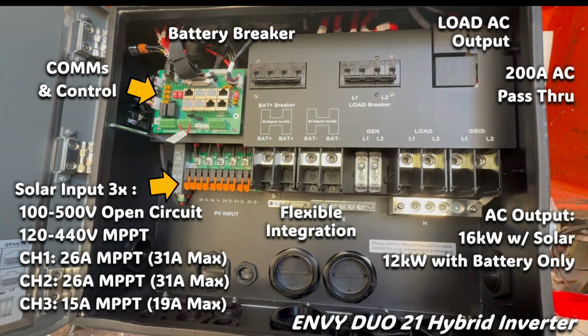Next up, the comms and control board allows you to have inverter communication to battery, the CT current transducers on your line for self-consumption, and then parallel connections if you have more than one inverter. Next up, the battery breaker. This is built into the inverter and allows connection of the battery system. You can see you have 2 positive battery connection terminals and 2 negative battery terminal connections. The battery terminals can handle about 4/0 copper. It's actually metric and 4/0 is an American number, but you get the drift. You can have plenty of battery cables leaving here.